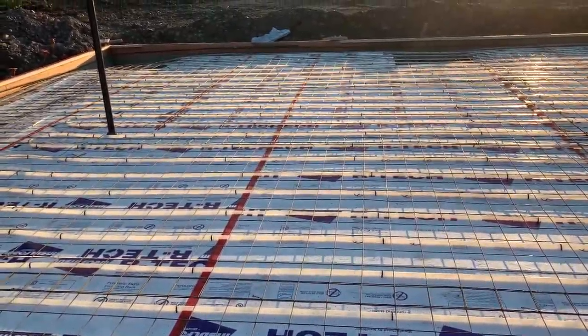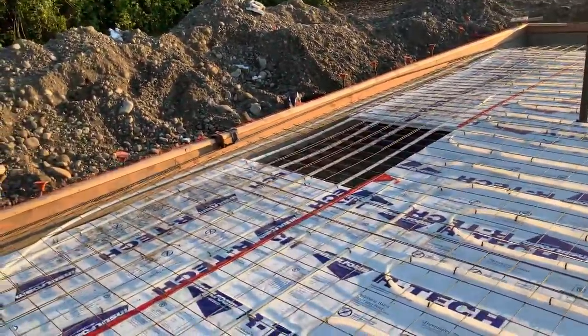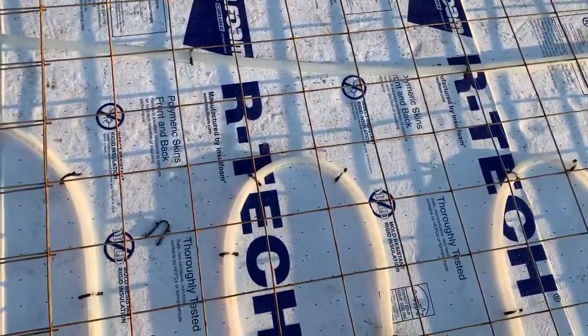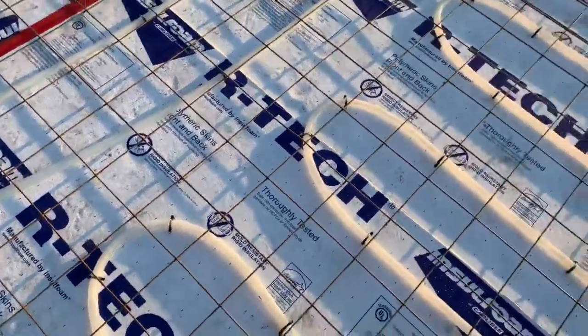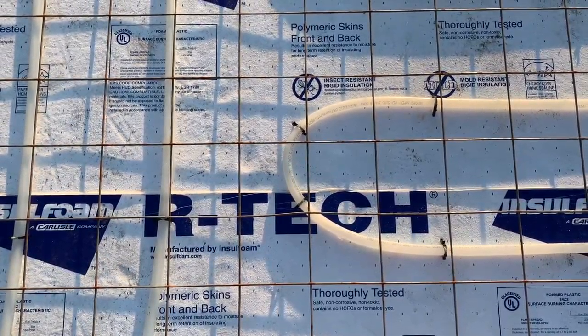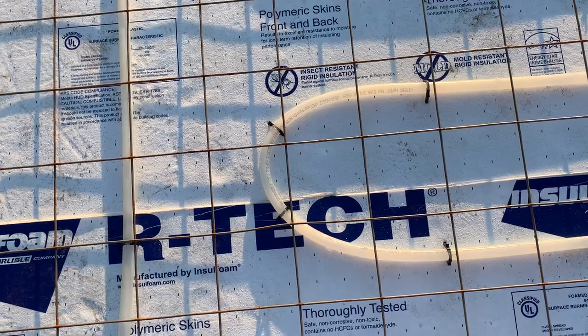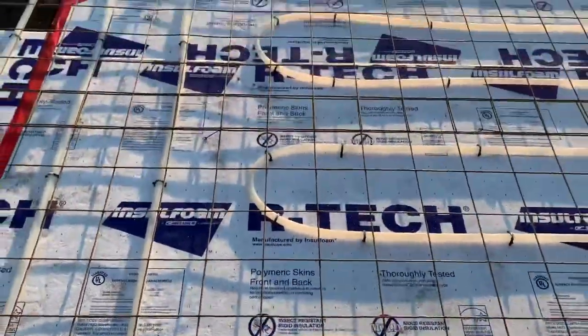It's important to have good planning done. I'll show you how we looped these tubes right here. We watched some videos on how to lay the tubes and the video said you have to clip it right at the peak and staple it at the peak, but from our experience we liked it on two sides — you can see the tubes don't wiggle as much, so it's easier to lay them.